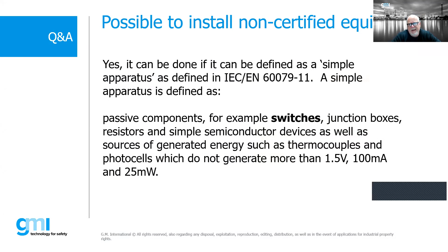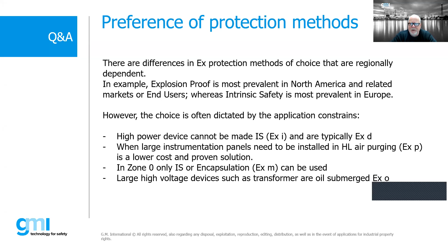Which is the most used protection method? I guess it depends on many things, the world you live in and the application you have. In generalities, for high power devices, typically we're going to use more EXD, we're not going to make them EXI. If we have non-switching devices, it makes sense to go EXE if we can. A lot of control panels, we might do purging. In some cases, high voltage switching devices, transformers, we might use oil immersion. So there's a lot of different protection concepts. There's not necessarily one size fits all, there's different ways to address these hazardous locations with protection concepts.